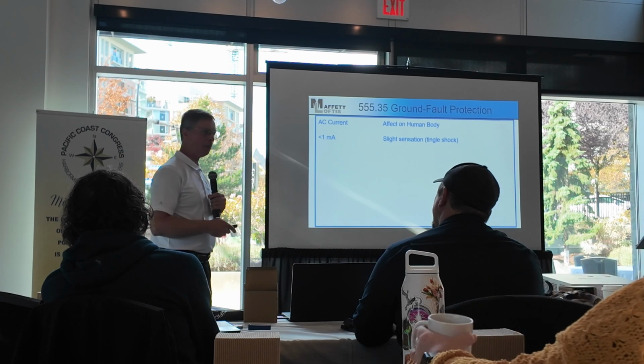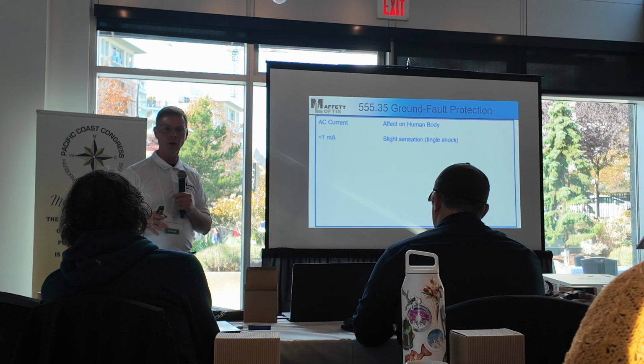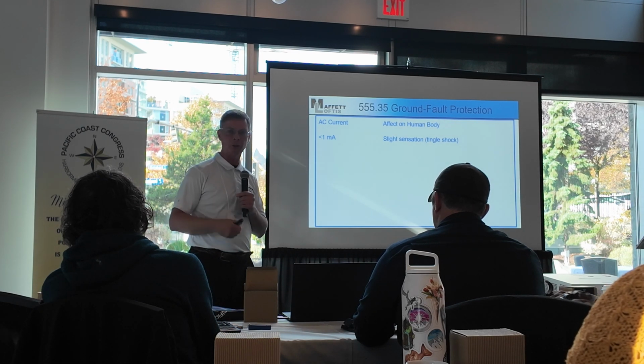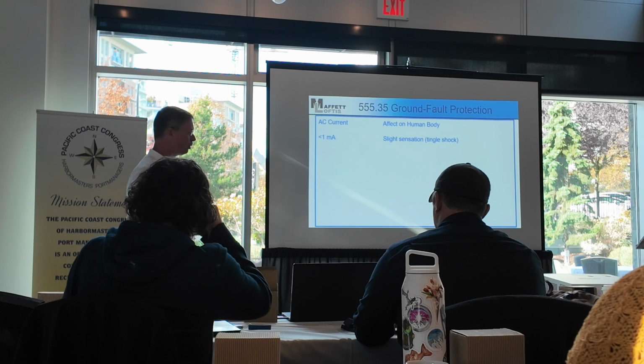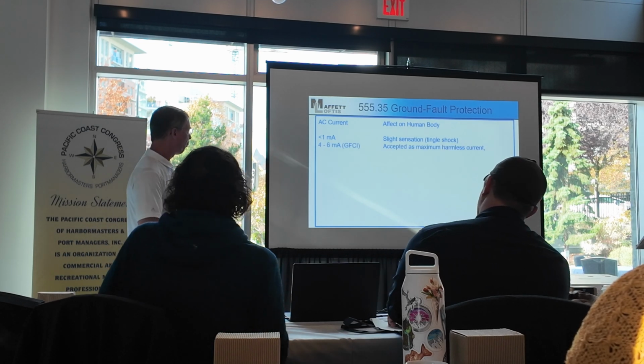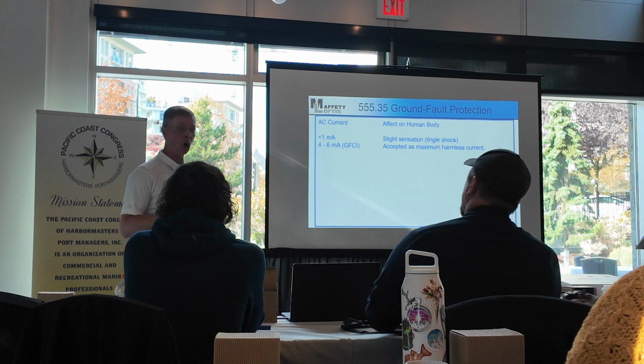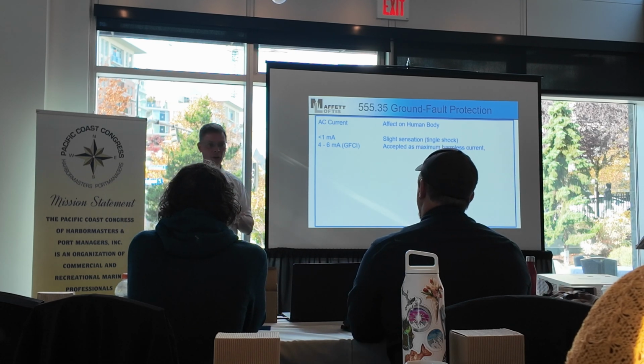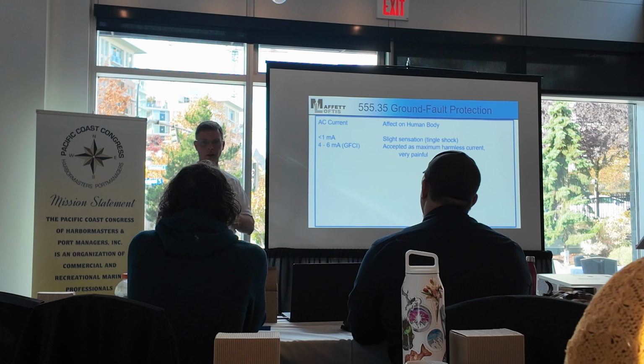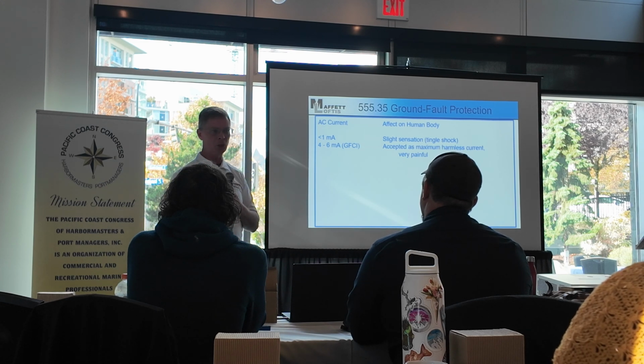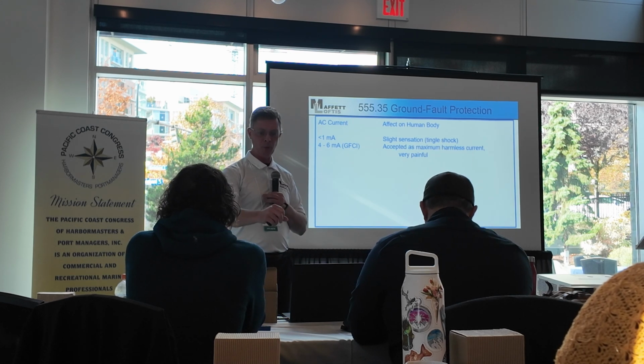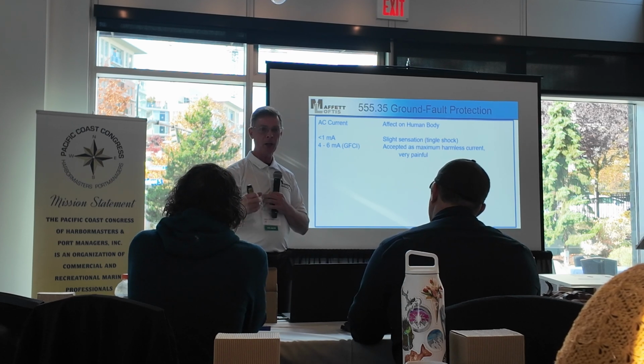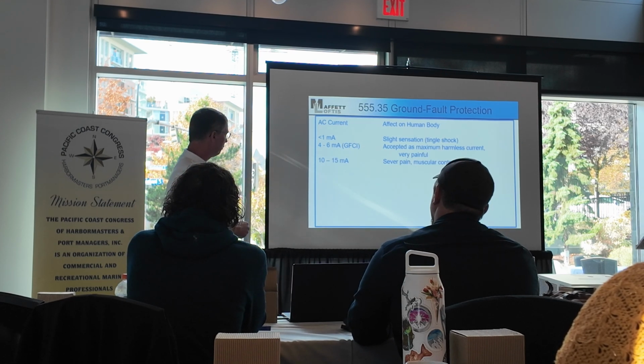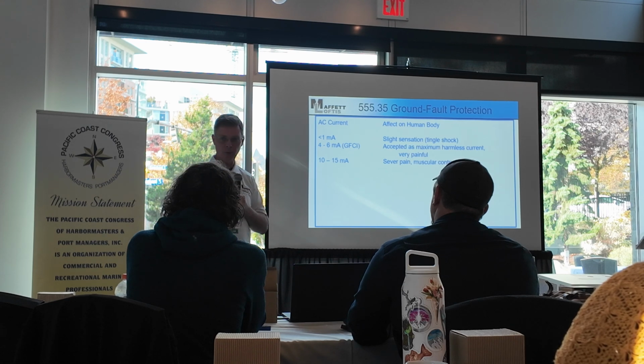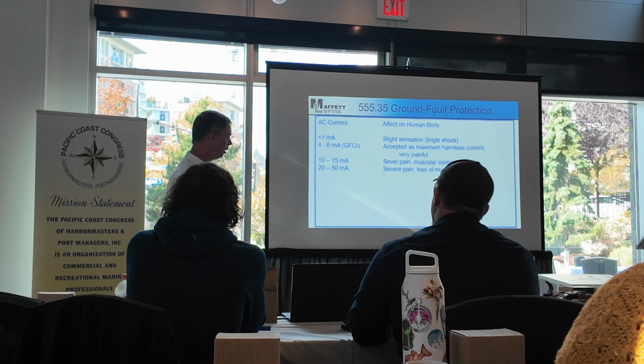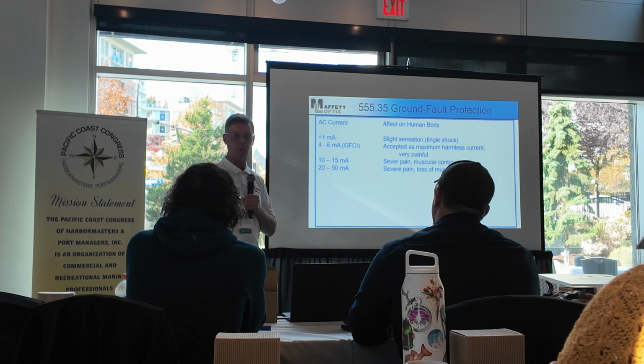With less than a milliamp, it's a tingle shock. It doesn't really hurt. You remember those TENS units for your back muscles and stuff. But less than a milliamp doesn't hurt. Okay. Now 4 to 6 milliamps is acceptable as harmless to the human body because you can still move, and boy, that hurts. I had 6 milliamps running on my arm, and it's all I could do to stand it. But I could move my hand. Okay, it wouldn't lock me up, but I could still move. If you get up around 15 to 20, you get severe muscle contraction, and especially up around 20 milliamps, you lose all muscle control, and your muscles will freeze up.